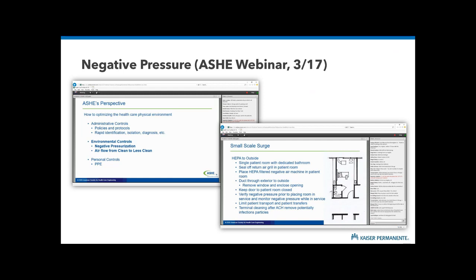It was unstoppable, really. I think at Kaiser we have 50, 75 rooms like the one that I showed you just a second ago, which is to say that we probably spent somewhere between $1 million and $5 million on temporary negative pressure room conversions. That number could be as high as 10 million. Nationwide, it's easy to estimate that U.S. hospitals spent hundreds of millions of dollars converting rooms to negative pressure in March and April of 2020. That is not money terribly well spent, folks, and it's not over. All of those temporary negative pressure rooms are going to need to get converted back. So it's going to cost us more to take them out than it did to put them in, because now it's biohazard waste. So we're not done spending a bunch of money on negative pressure.